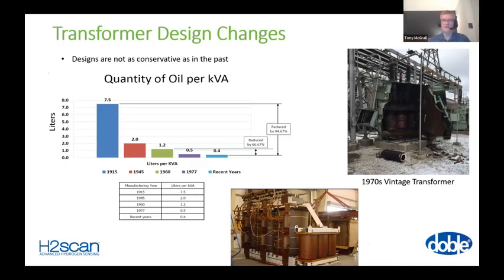I must admit, I did feel a little wary earlier because Mose was talking about how often you should maintain transformers. When I was at National Grid US, we said maintenance should occur at least once every 12 years. That's when maintenance becomes due, and it's not overdue until it becomes 15 years. So you've got a 3-year gap to do your maintenance. And once every 12 years for us was adequate, mainly for the transmission side.